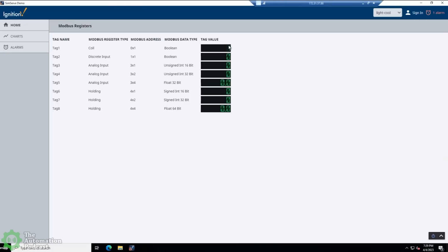I'm going to get just a little bit fancier here. I'm actually going to skip down to tag 4, because I think that's probably the most enlightening next example to show. And I'm going to go into SimServe, and we're going to toggle some registers to get a value displayed here on tag 4. Now, before I jump back over to SimServe, let me just point out, this is an unsigned integer 32-bit. And there's different nomenclatures out there. Some people would call that an unsigned long. Some people would call that an unsigned double int. Some people would just call that an int.